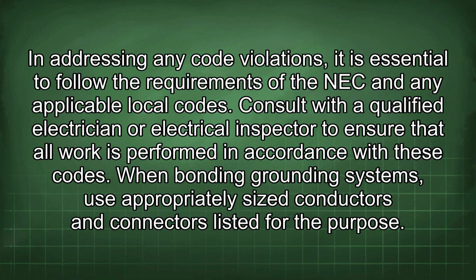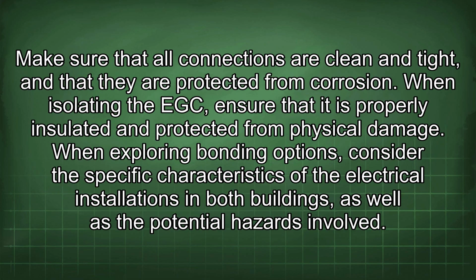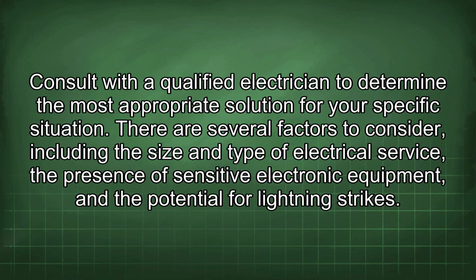In addressing any code violations, it is essential to follow the requirements of the NEC and any applicable local codes. Consult with a qualified electrician or electrical inspector to ensure that all work is performed in accordance with these codes. When bonding grounding systems, use appropriately sized conductors and connectors listed for the purpose. Make sure that all connections are clean and tight, and that they are protected from corrosion. When isolating the EGC, ensure that it is properly insulated and protected from physical damage. When exploring bonding options, consider the specific characteristics of the electrical installations in both buildings, as well as the potential hazards involved. Consult with a qualified electrician to determine the most appropriate solution for your specific situation.